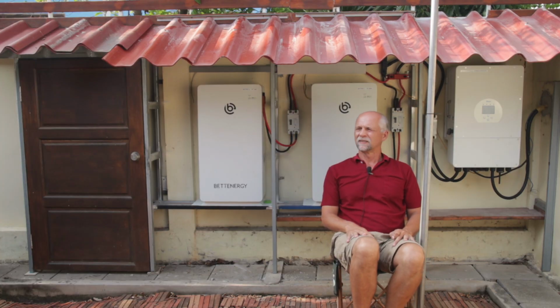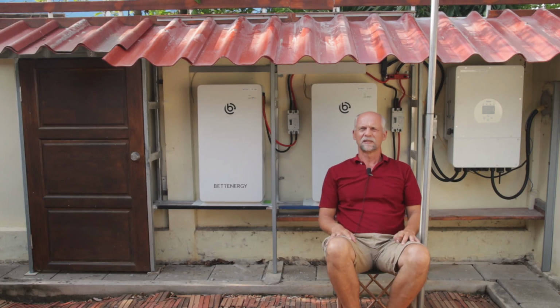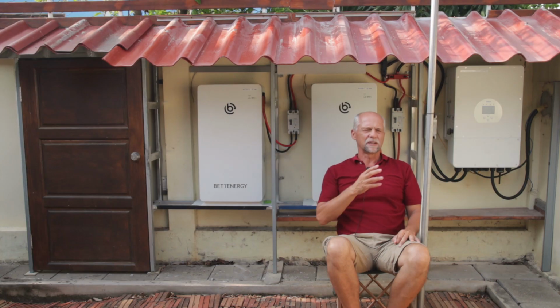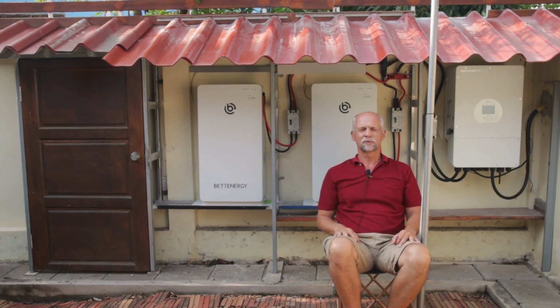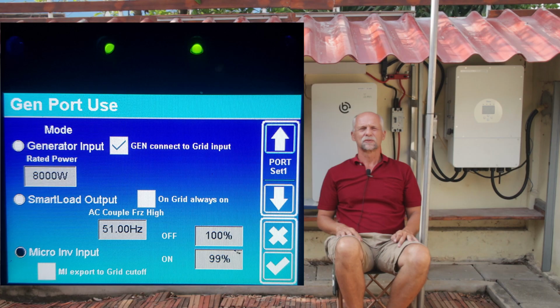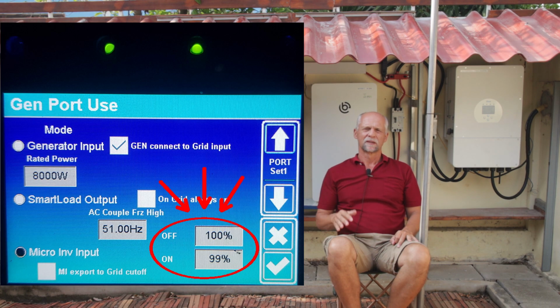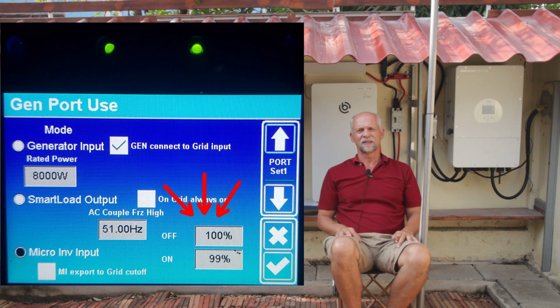Last time I ended by telling you how the communication is established between battery, BMS and the inverter. So what I still had to do: since we are AC coupling on the grid input on the hybrid inverter, I had to go back to the generator port page, and because our reference changed from battery voltage to percentage, I had to change the SOC values at the microinverter inputs there.